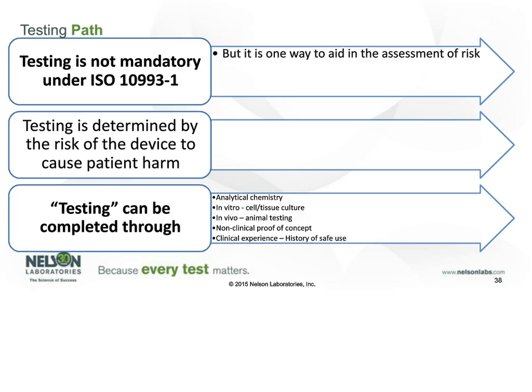And these are some of the ways that we can do testing, quote unquote. So we can do in vivo, and that's the animal tests. We obviously want to try to minimize that as much as possible, not just because they're usually the most expensive and long tests, but because of the animal impact. We really want to try to do other approaches first. For example, in vitro evaluations. Can we be more sensitive with in vitros? We are investigating new in vitro tests for irritation and sensitization that both look very promising, and initial results seem to be that they may be a little bit more sensitive than the animal models. So they may be able to be used as a screening test before jumping right into the animal tests. We're working on round robins, specifically on the in vitro irritation right now in the ISO group, to try to add that test to the standard.